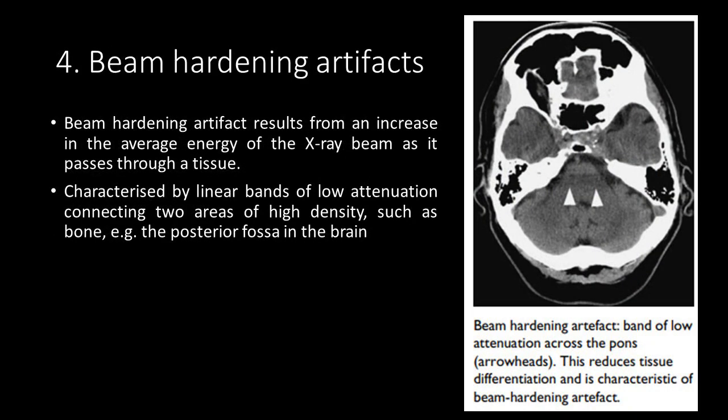Lastly, we will discuss beam-hardening artifacts. Beam-hardening artifact results from an increase in the average energy of the X-ray beam as it passes through a tissue. Think of CT as using a spectrum of radiation energy. Low-energy radiation is filtered out by high-density structures such as bone, leaving higher-energy radiation that is less absorbed by soft tissues, causing low-attenuation streak artifact. It is characterized by linear bands of low-attenuation connecting two areas of high-density, such as bone, like the posterior fossa in the brain. It can be reduced by using a filter to adjust the spectrum of radiation and by post-processing software.